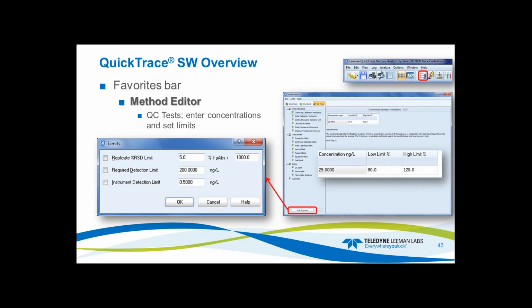This will give you a value, for example, if it's above 100 microabsorbance units and you want 5% RSD, you add that. So if it's greater than that, it'll throw a flag. If it's less than that, the system doesn't care. It'll just move on. And also, if you check required detection limits and or instrument, it will give you a less than or equal to that value there.